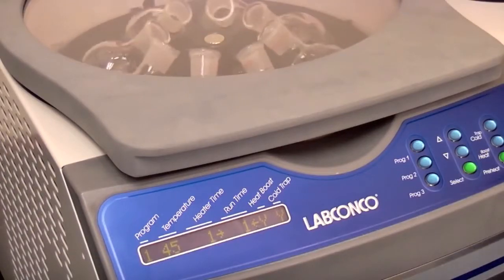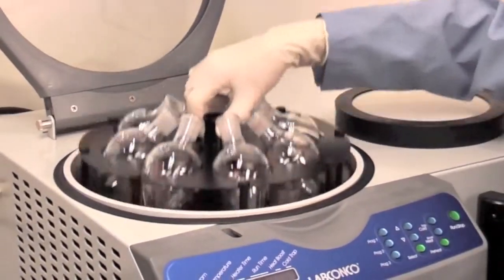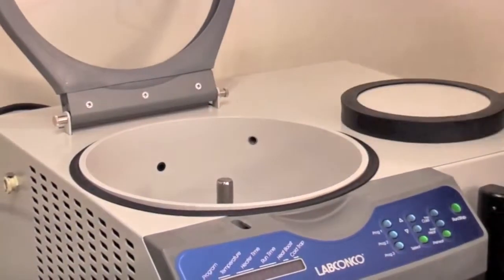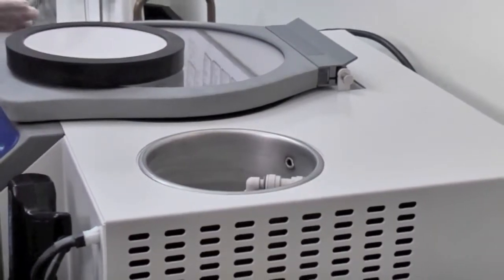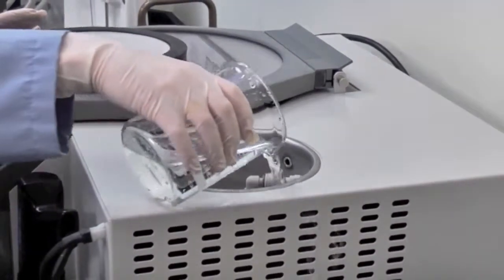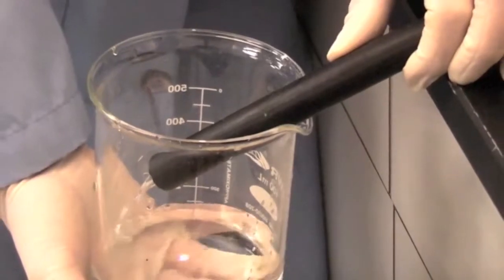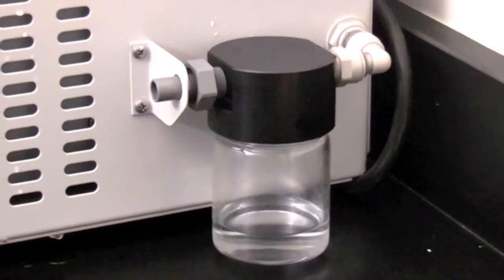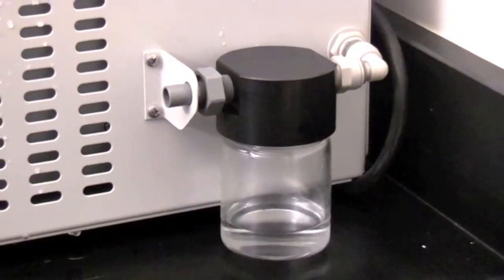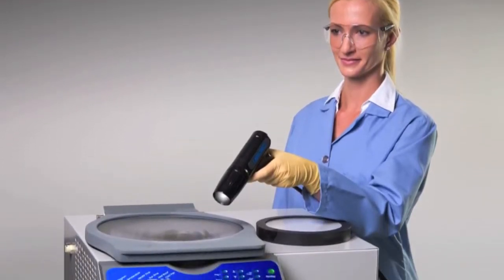Remove the samples when they are dry. Defrost and drain the cold trap, making sure to close the port after draining. Check the vacuum pump exhaust trap and empty if necessary. The CentriVap Complete is the complete package for evaporation.